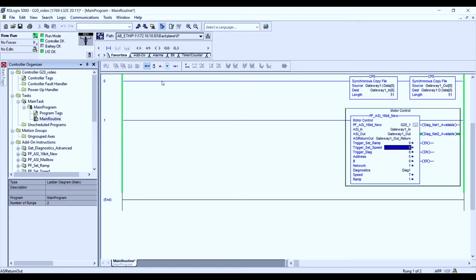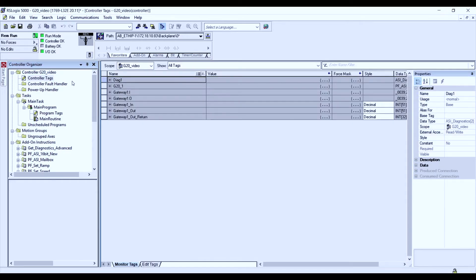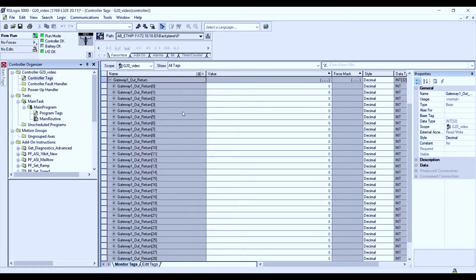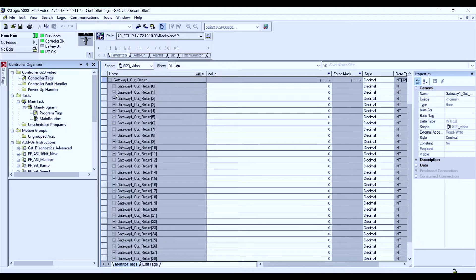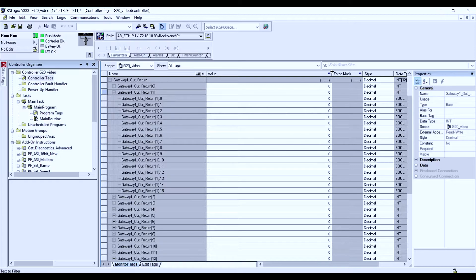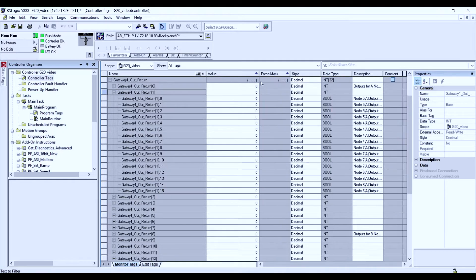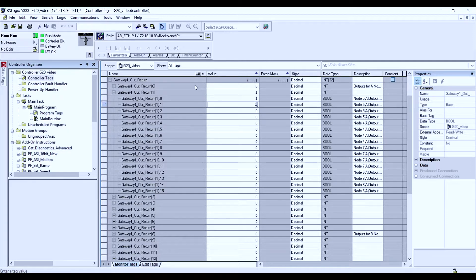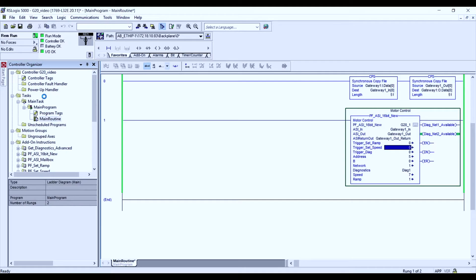The first thing we must do is go to our controller tags. In our controller tags, we need to set the bits, the output bits corresponding to our node 5. In this location, we can see that node 5 bits are represented by bits 0 and 1. So as I trigger the bits here as 1, I start my motor running. And the motor is running at now the speed of 7, corresponding to 7.26 volts.